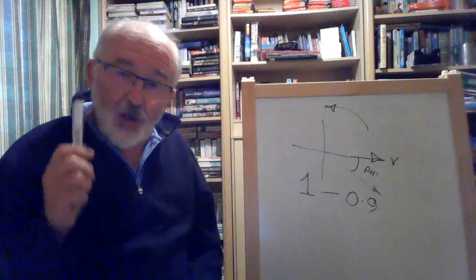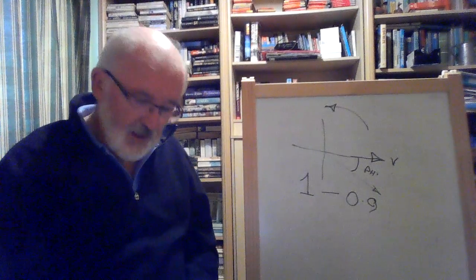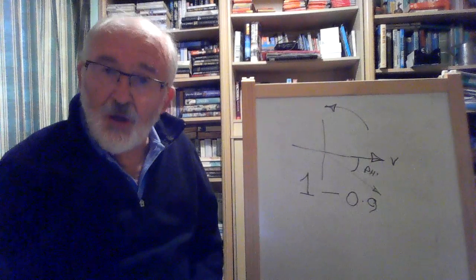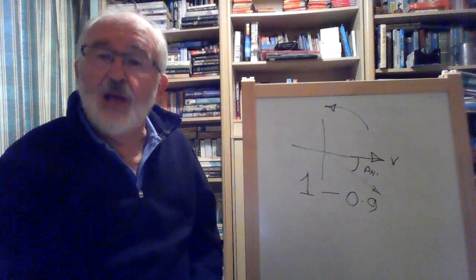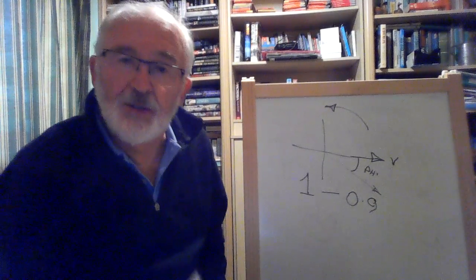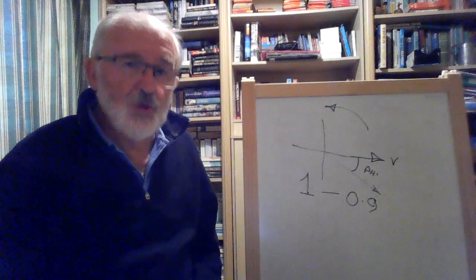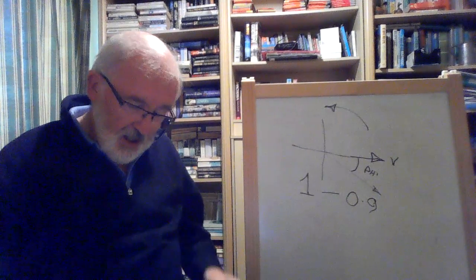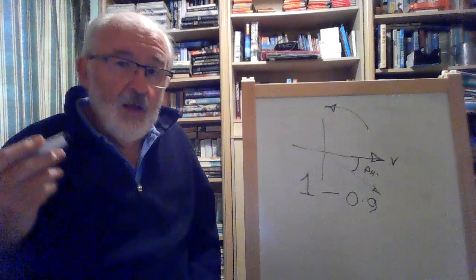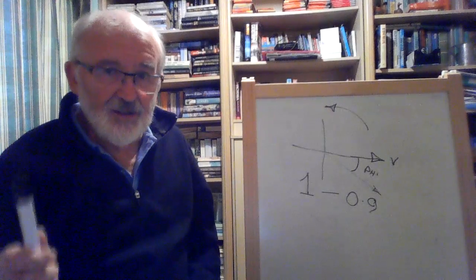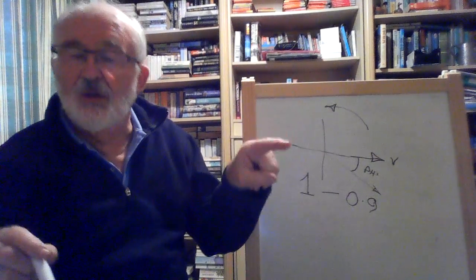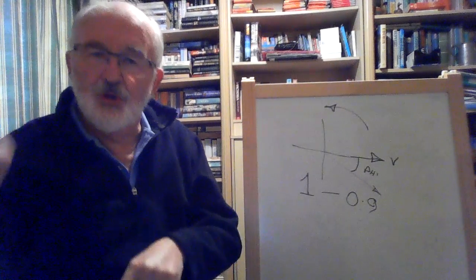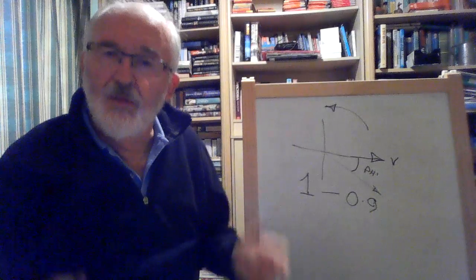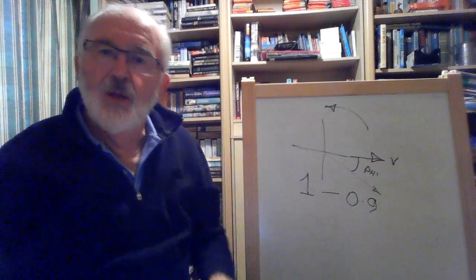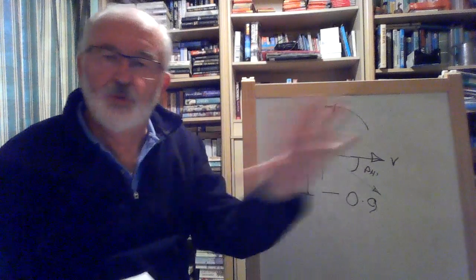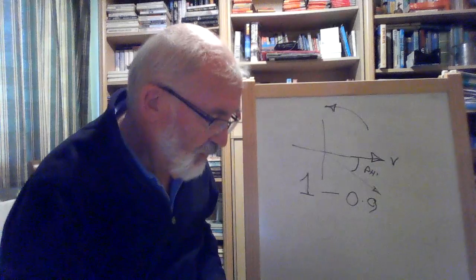Should an earth occur in one line, red, yellow, or blue, one of those three phases, then you would get an alarm on your earth monitor, but nothing else would happen. It doesn't mean you've then got to go out and find where the earth is, which is a problem, but it needs to be done. But it won't black the ship out. In order for that to happen, you would need a second earth on another line. So if you had a first earth fault on the red line and a second earth fault on, say, the blue, then you would actually interconnect the two earths through machinery, and you would actually lose your power.